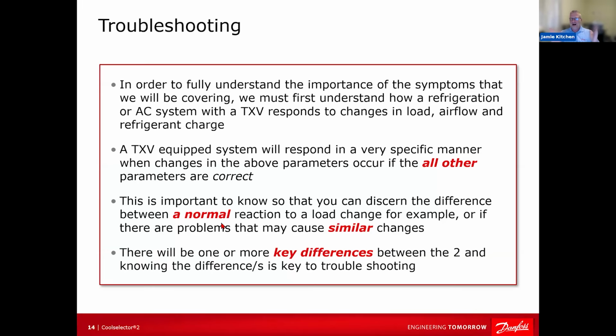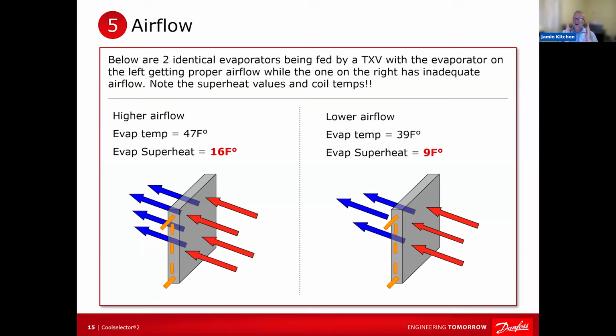So what I usually do, keep in mind that the class that I normally put on is quite a bit longer. But in order to properly troubleshoot, you can look at a form and you can say, is it this or is it this? And you can check the box off, and then you can be a robot if you want. But to do proper troubleshooting, you need to know, what would the system be doing if it was running correctly under these conditions? How much humidity you have? What's your temperature? How much load? Whatever. What's my voltage? All these things. If it was running correctly, what would I see? And then you compare that to what you see now, and that difference then is how you identify the problem.